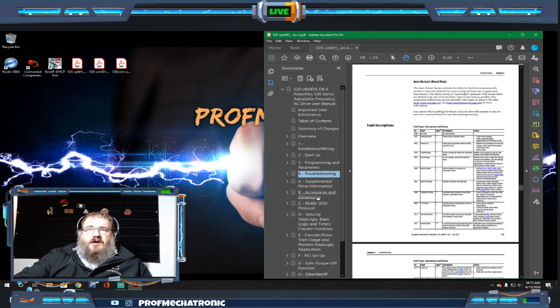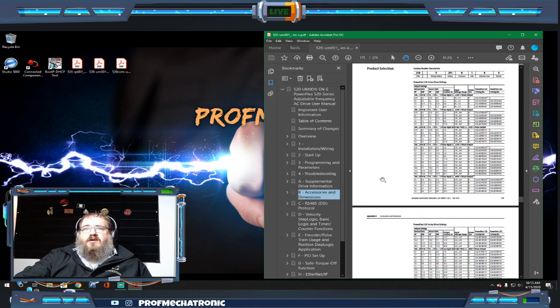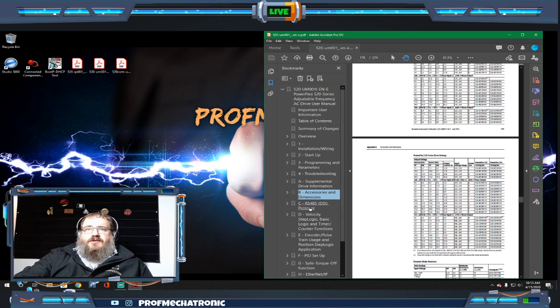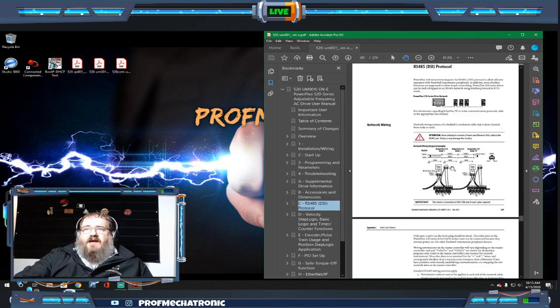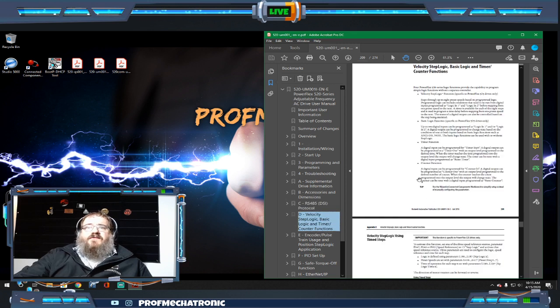Here you see the accessories—what other accessories can you buy for the drives, how do we set those up. The RS485—how do we do communications over RS485, that serial communications setup, the DSI protocols. How do we do velocity step logics, basic logics, timer counter functions? These drives are pretty advanced, where you can take information that we normally handle in a PLC and do it in the drive instead.